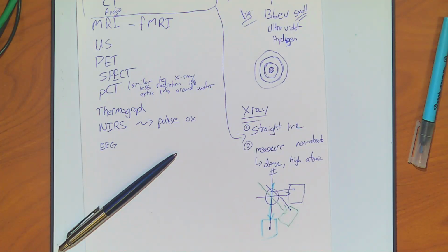And we'll tag different areas of your body with a phase shift. So every area in your body will impose a slightly different field and phase, so we can measure back what the field and phase is so we can locate it in space. Right? And we do all these unique measurements at these different frequency and phase combos. What we're doing is actually rebuilding your frequency space. So we're going to be doing our measurements, instead of in regular space, in Fourier space. You reconstruct the image by doing an inverse Fourier transform.